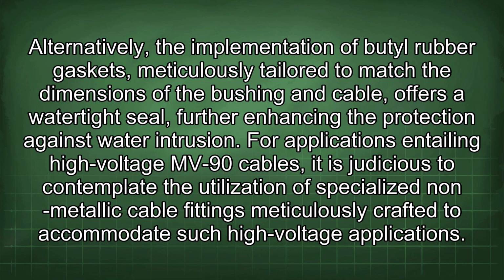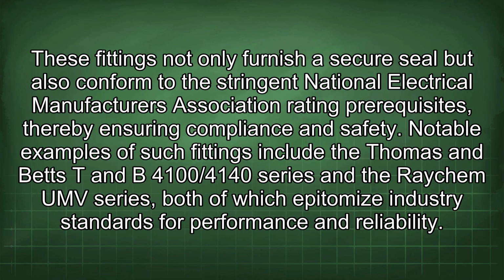For applications entailing high-voltage MV-90 cables, it is judicious to contemplate the utilization of specialized non-metallic cable fittings meticulously crafted to accommodate such high-voltage applications. These fittings not only furnish a secure seal but also conform to the stringent National Electrical Manufacturers Association rating prerequisites, thereby ensuring compliance and safety. Notable examples of such fittings include the Thomas and Betts T and B 4100/4140 series and the Raychem UMV series, both of which epitomize industry standards for performance and reliability.